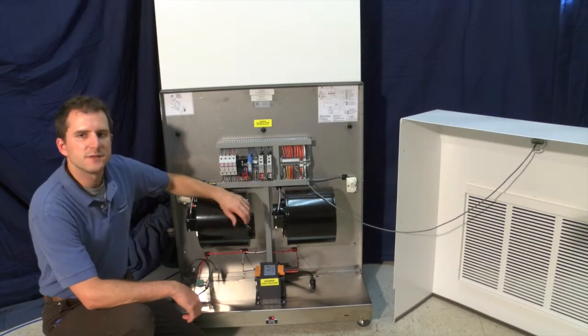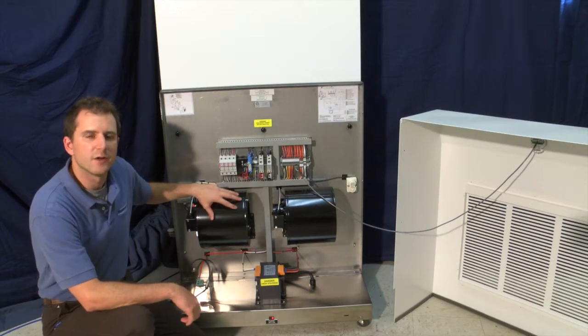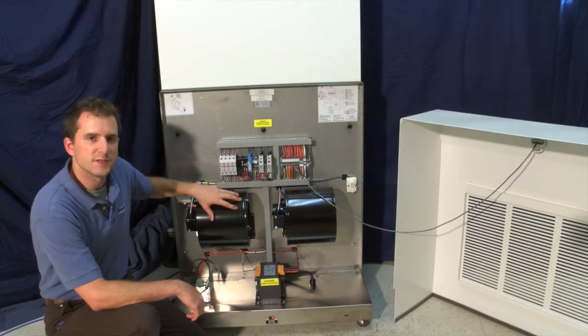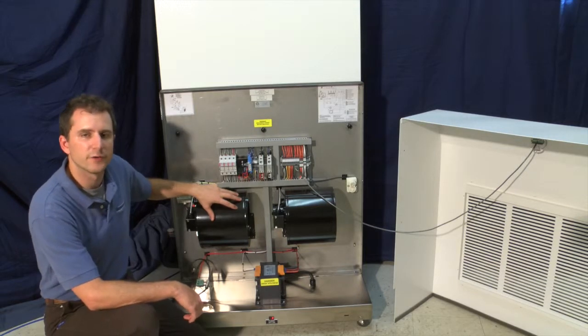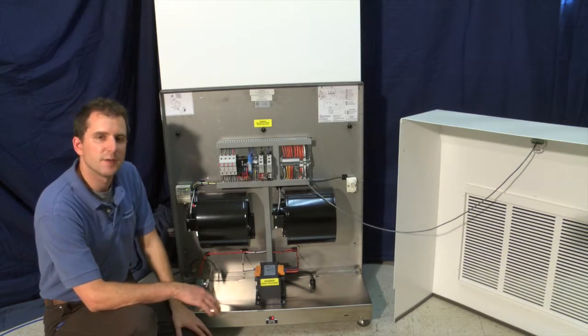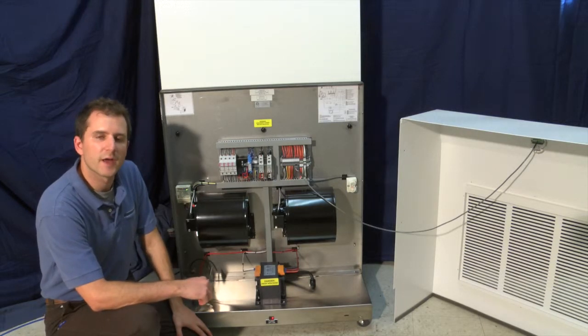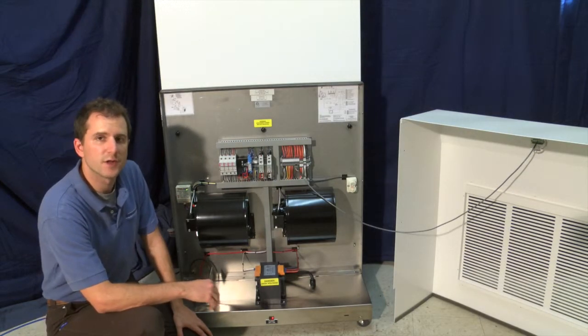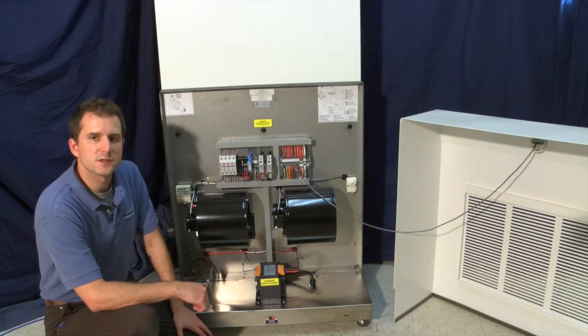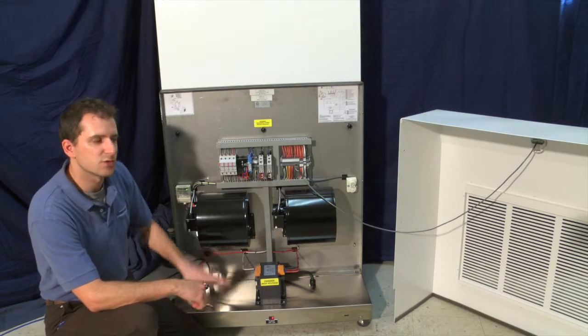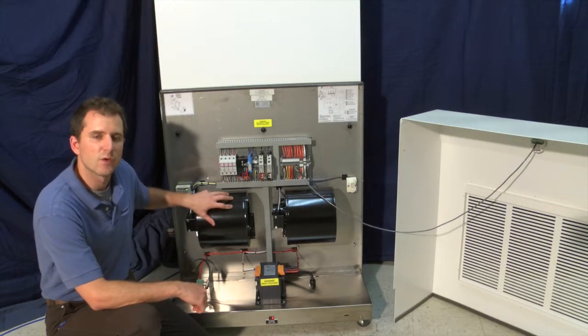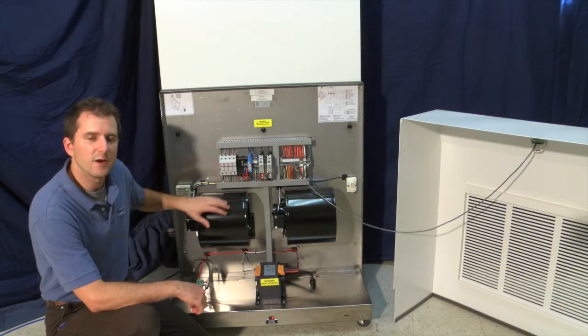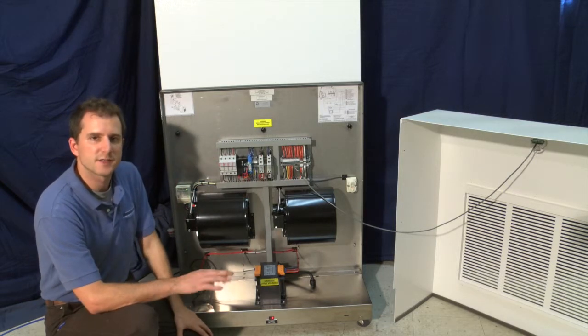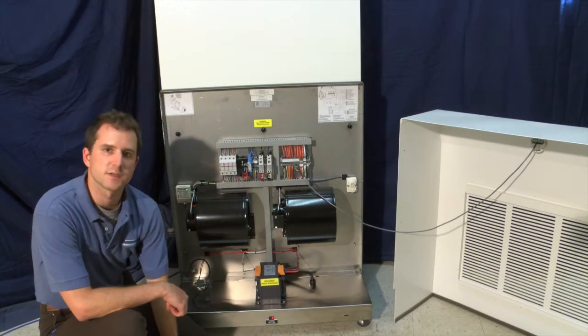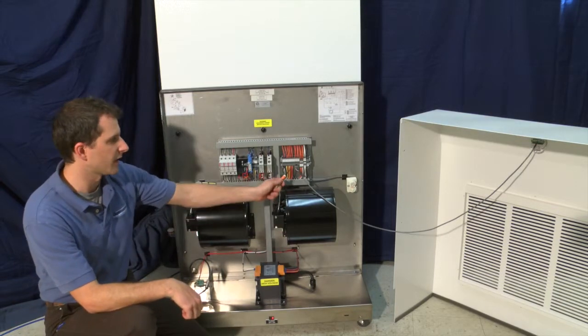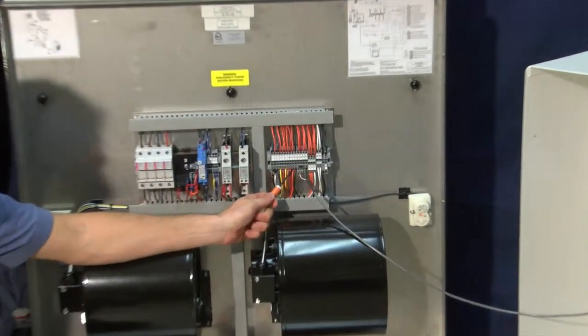By default, the fans inside the mist-free humidifier will cycle on and off with the transducers. This means the fans will turn off when there is no call for humidity. Some applications that keep high levels of humidity can find an organic growth inside their chute due to the high level of humidity. The easiest way to stop this is a simple switch which will allow the fans to run continuously whether there's a call for humidity or not. The air movement in the chute will dry it out and stop that organic growth from happening. This is a simple process that's done at the terminal block located on the interface plate.